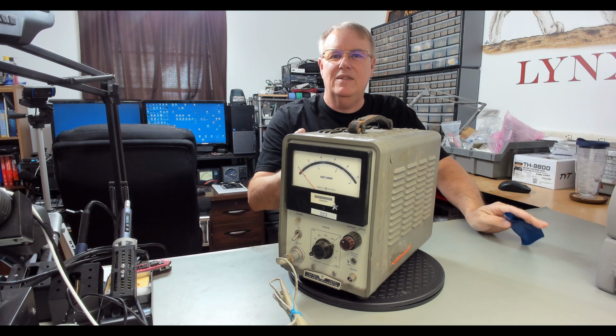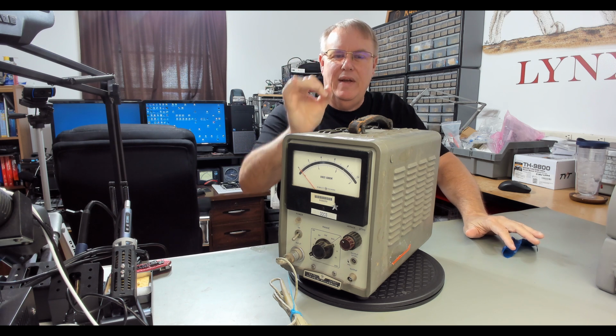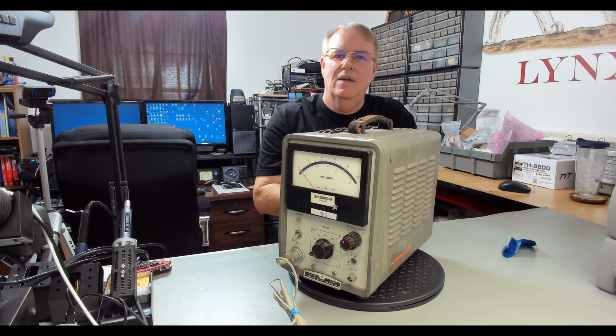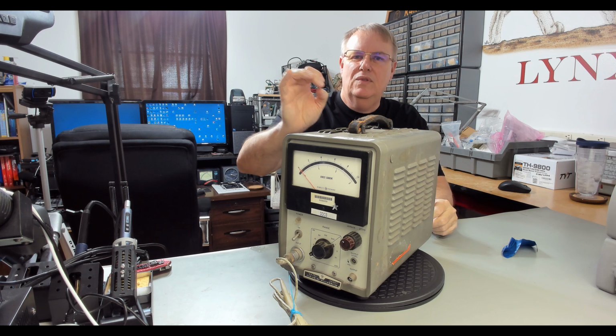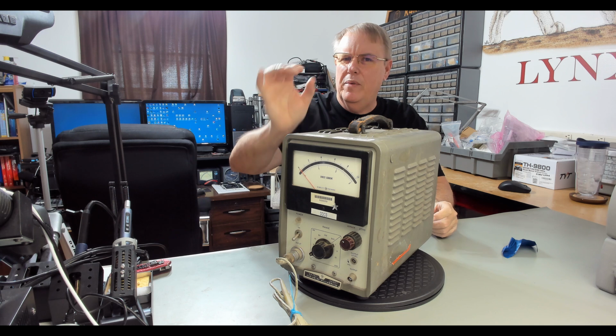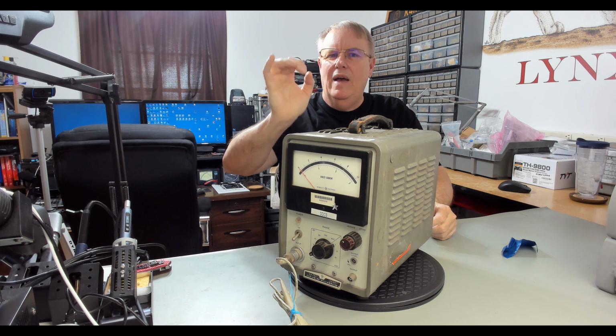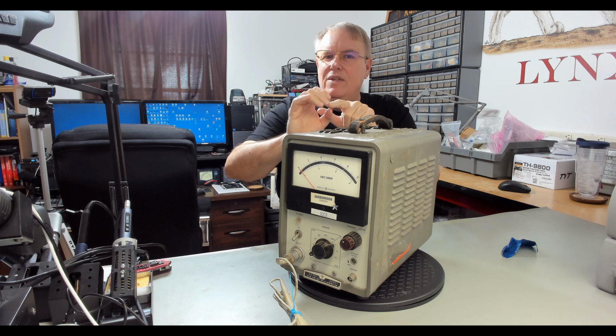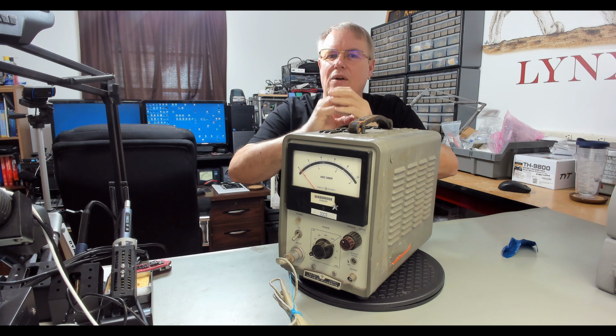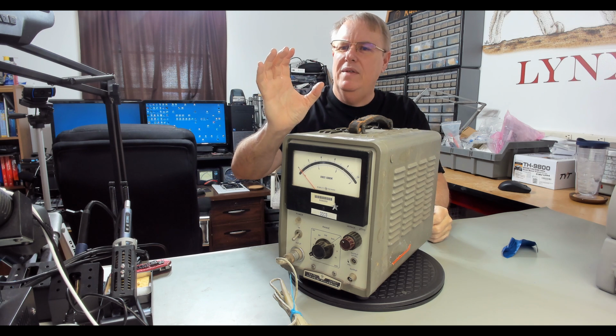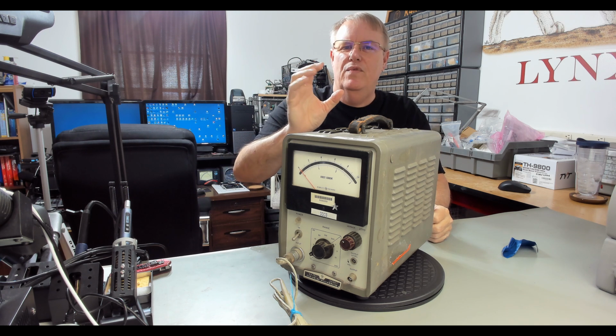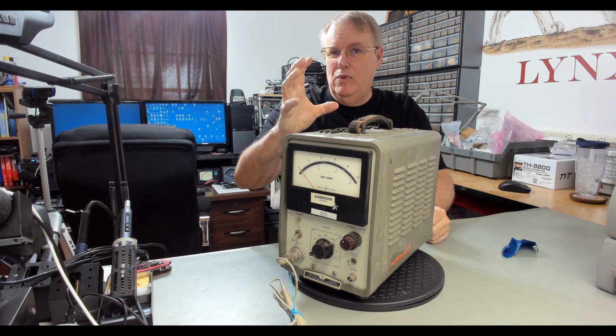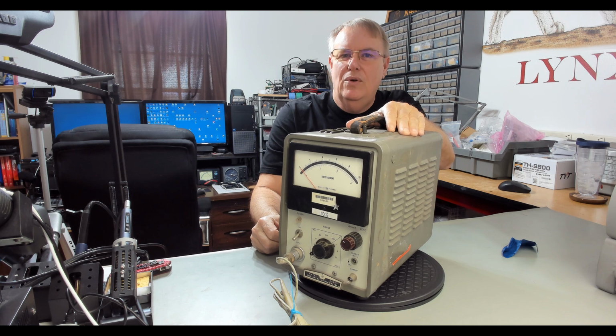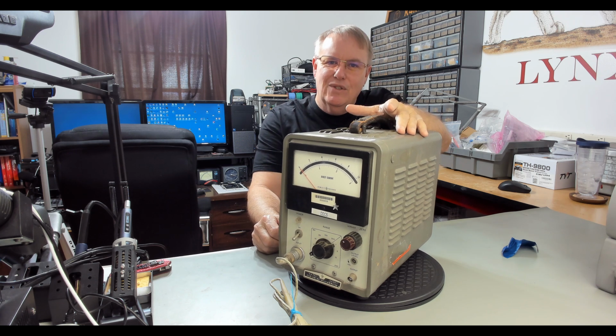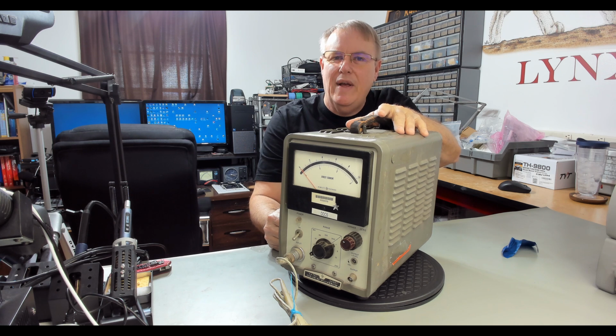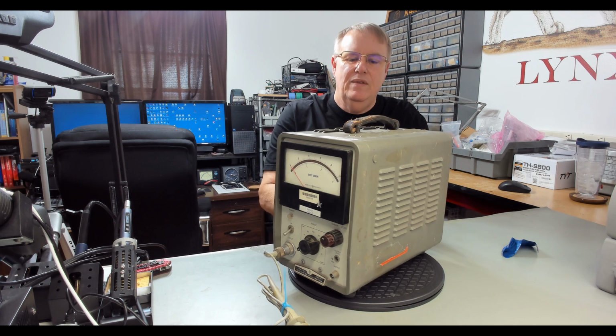It generates its own AC signal on one side of the ferrite clamp, and it senses on the opposite side. And so what happens is if you put a known signal oscillating, I think it's 40 kilohertz, don't quote me on that, but a 40 kilohertz signal at a known level, it will vary depending on a DC current, because the DC current creates a field, it just doesn't cycle. And when that field builds up, it basically buffers the AC signal, so it varies it. And it varies it based on the amplitude of the field. And so this system creates its own signal, and then it looks at the change in it to tell you how much current in DC is running through the clamp. So pretty cool.